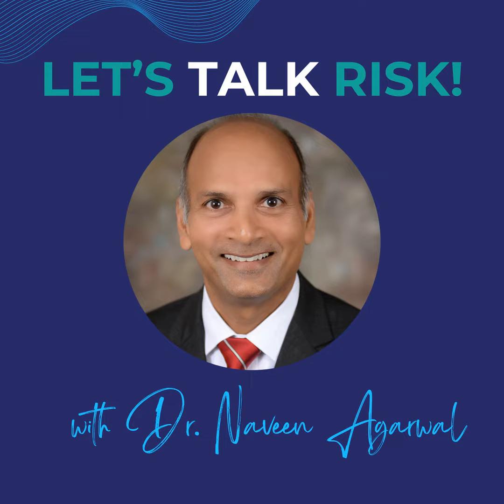Because I think, Ed, you can probably say a little bit more about that. There's a traceability requirement in 14971, correct? To all hazards. Yes. Yep. Correct. Yeah. And especially when you're adding AI and software, right? Yeah. You need that traceability. Yep. So it doesn't matter how you do it, but you must connect it somehow and show traceability. That's the whole point. Yep.